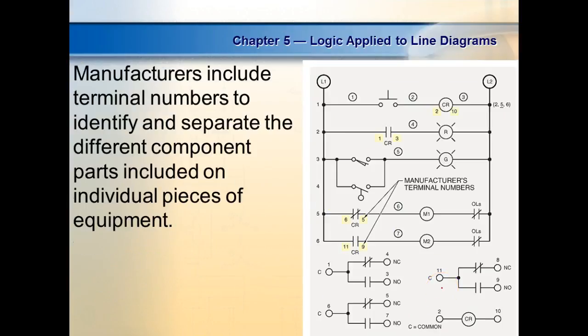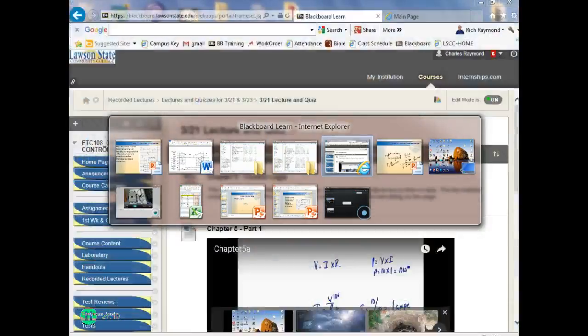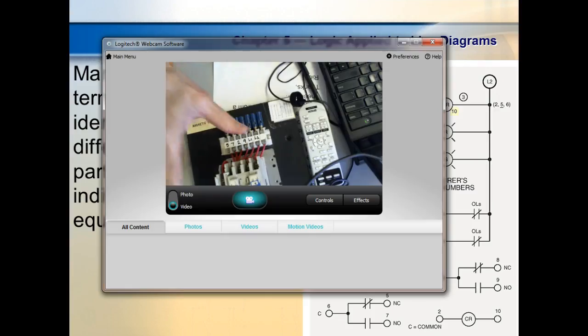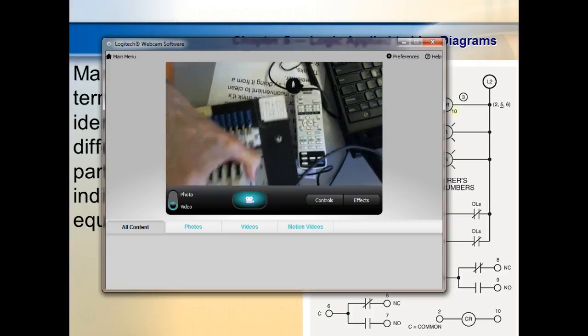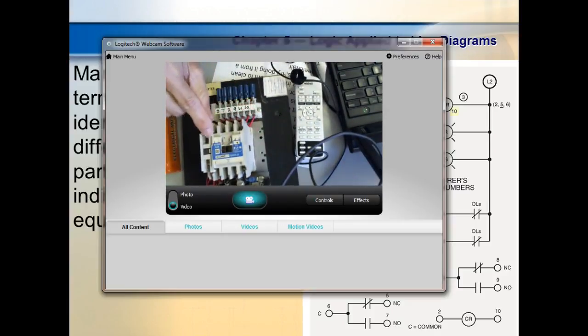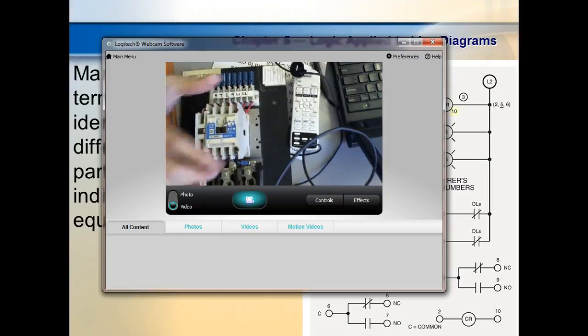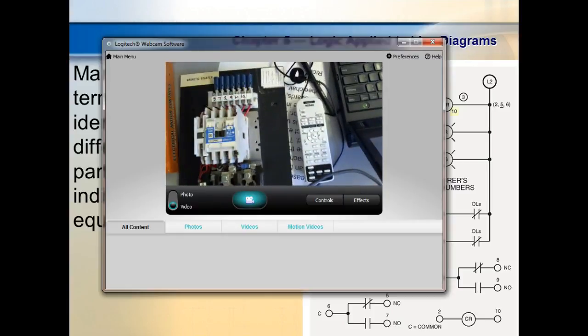These are what we call manufacturer numbers, and we're going to do this a lot. When you buy a relay or anything like that, it's got contacts, and it's going to have numbers on it. These numbers were assigned by the manufacturer. These have numbers here, and what they've done on our trainers is transposed the numbers up here to these banana plugs, but on the wrong side of it.